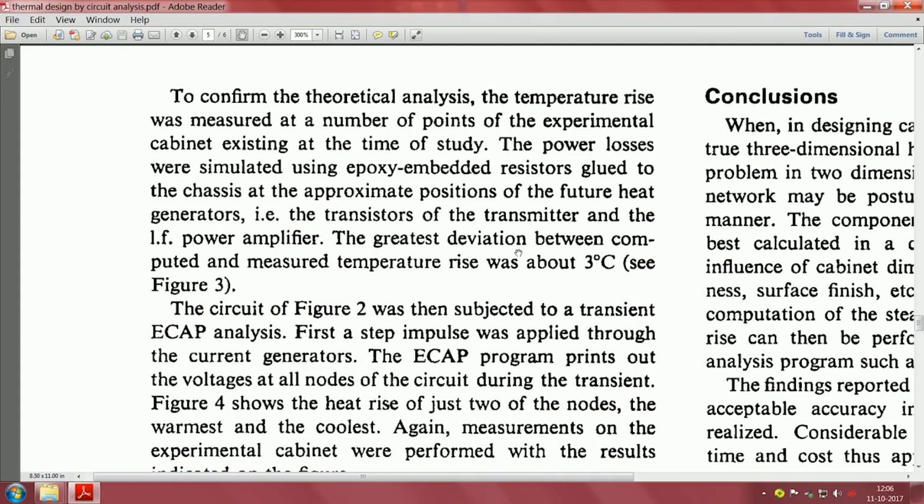Can you see it? The only way is you take a small area, and in the case we were in it was possible, we are trying to simulate point things by keeping the, what do you call that, resistor directly into another small case. And if we knew that it is going to be a small heat generating device, we used to take a 30 mm by 30 mm plate and then use resistors which can be directly bolted onto it.